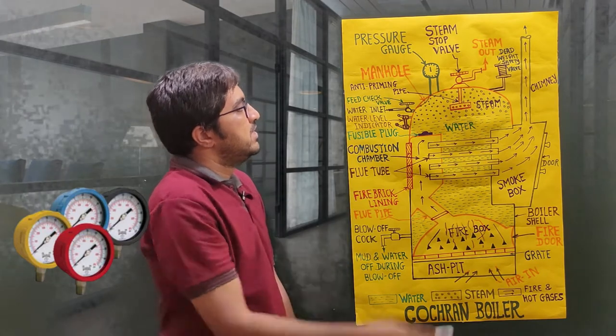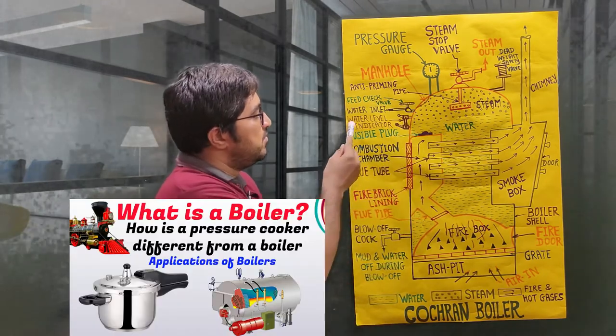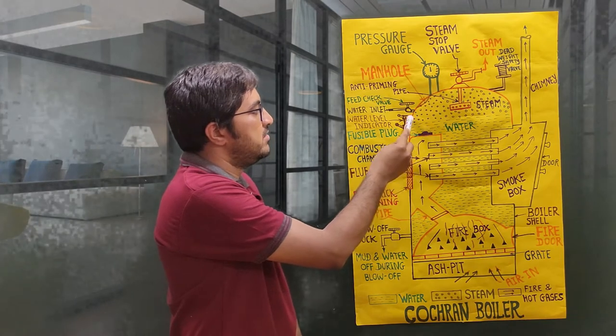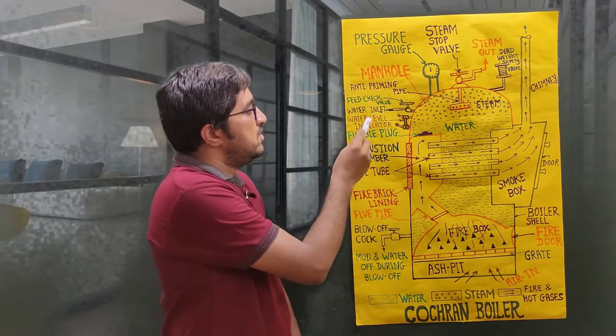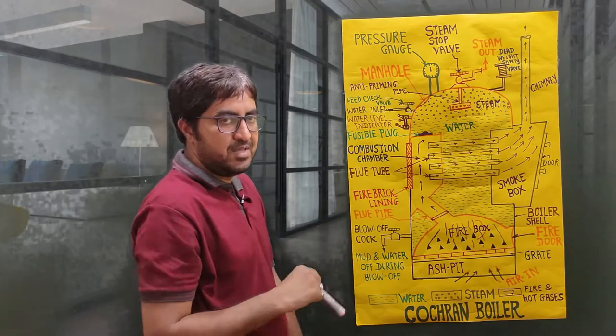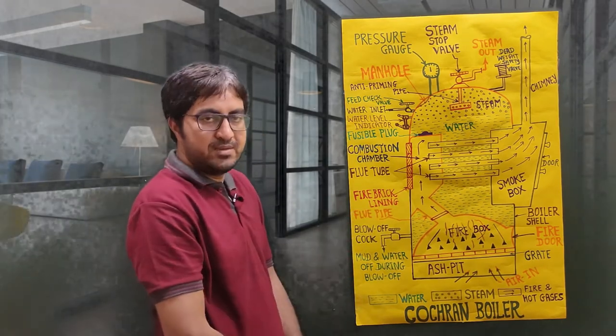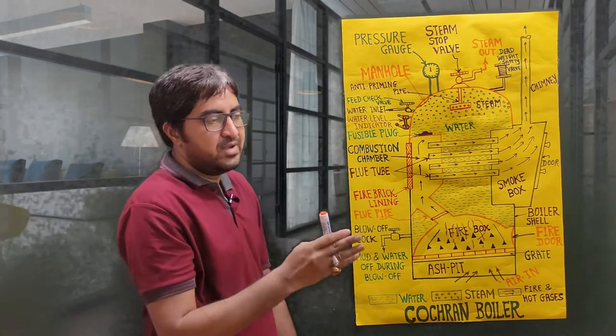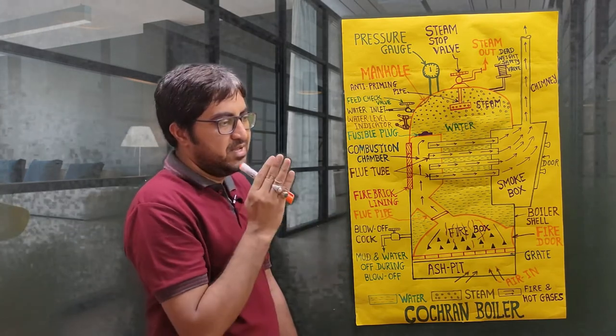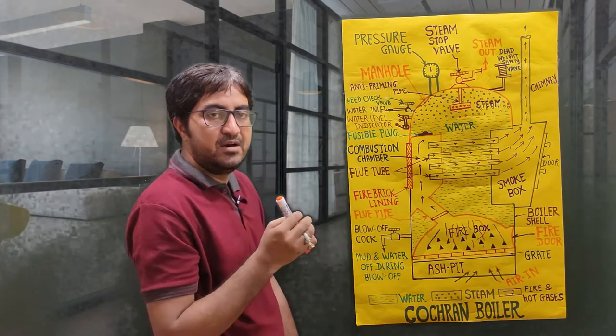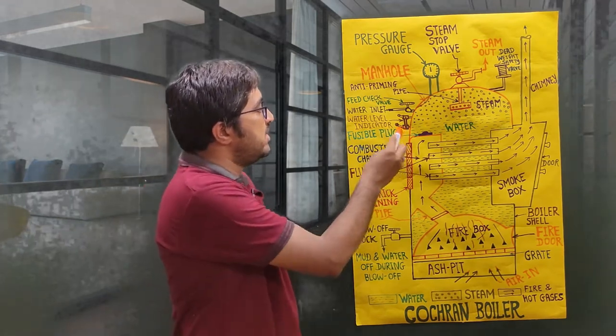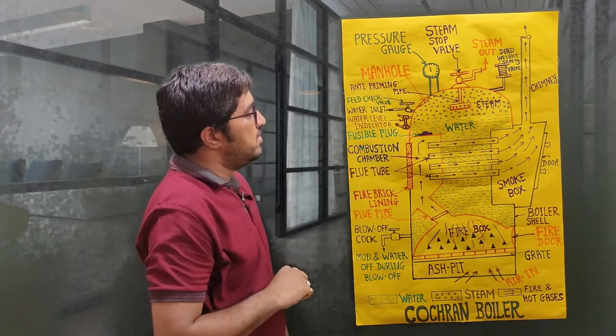The first mounting is the pressure gauge, whose function is to measure the pressure. The water level indicator has one end connected to the water side and the other end connected to the steam side, indicating the level of water inside the shell. As discussed in a previous lecture, boilers use two types of equipment: mountings — parts necessarily required to operate the boiler — and accessories, which are not necessarily required but increase the efficiency when used.